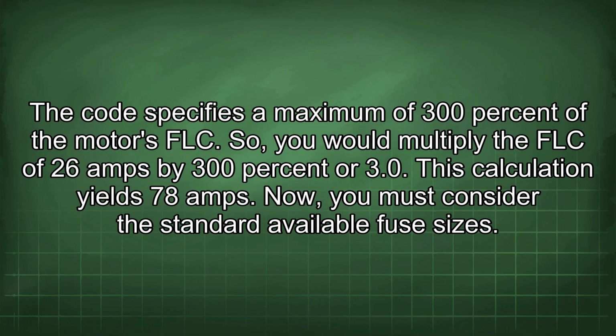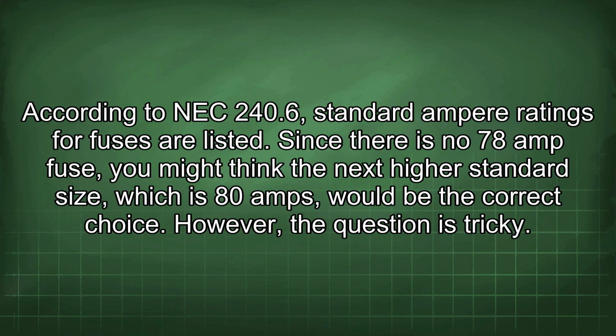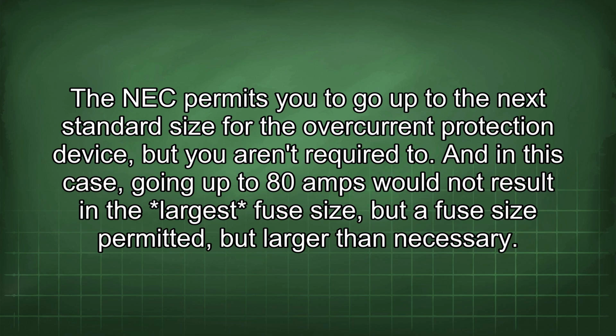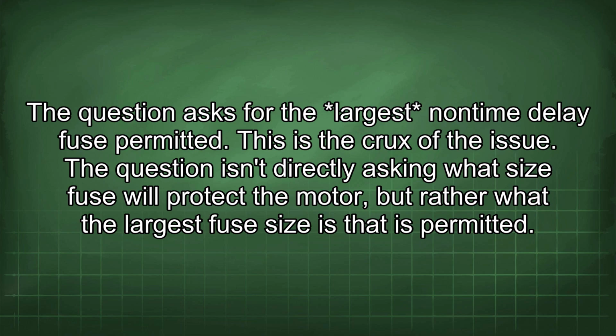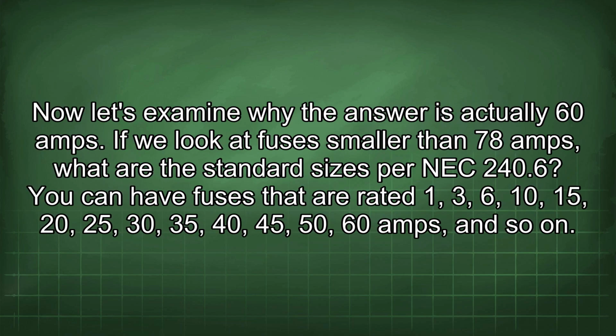Now, you must consider the standard available fuse sizes. According to NEC 240.6, standard ampere ratings for fuses are listed. Since there is no 78 amp fuse, you might think the next higher standard size, which is 80 amps, would be the correct choice. However, the question is tricky. The NEC permits you to go up to the next standard size for the overcurrent protection device, but you aren't required to. And in this case, going up to 80 amps would not result in the largest fuse size, but a fuse size permitted, but larger than necessary. The question asks for the largest non-time delay fuse permitted. This is the crux of the issue. The question isn't directly asking what size fuse will protect the motor, but rather what the largest fuse size is that is permitted. Now let's examine why the answer is actually 60 amps.